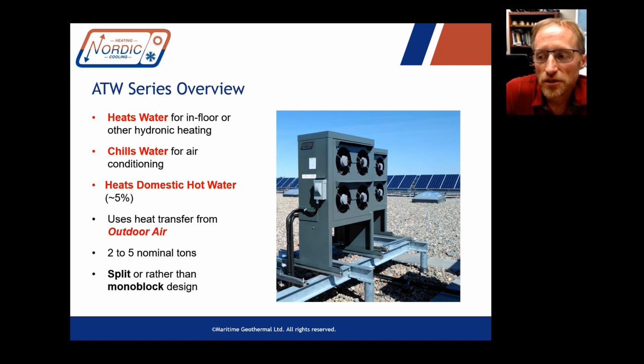Well, there are different ways you can do it. Most installations just use one buffer tank, and they do a seasonal switchover. Gotcha. Okay. So from cooling to heating, and you would do that by providing the heat pump a dry contact R to O, so an O signal basically. That would usually be done by a zone controller or something like that. But there is a built-in function in the control board, which I'll show you in a minute, that can switch back and forth automatically and heat one tank and cool another tank.